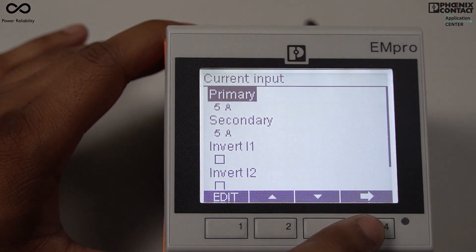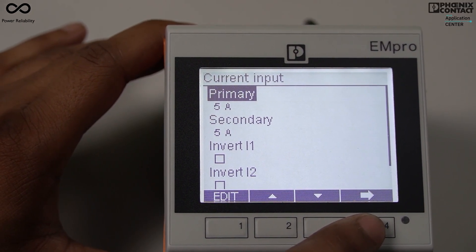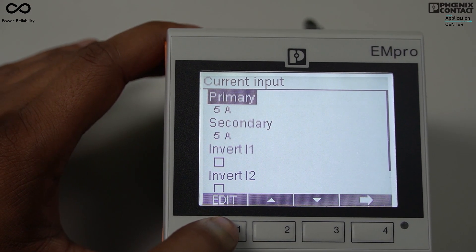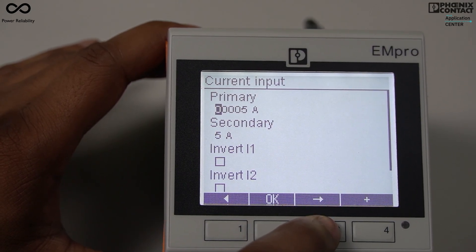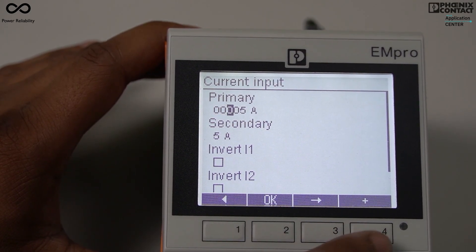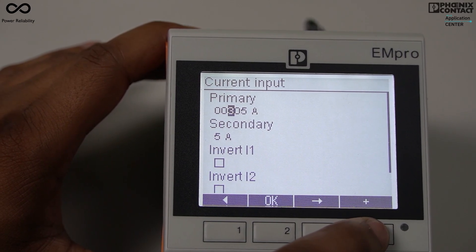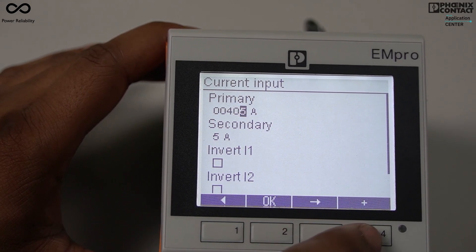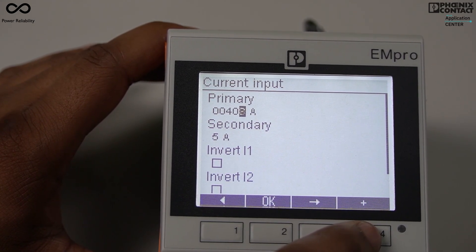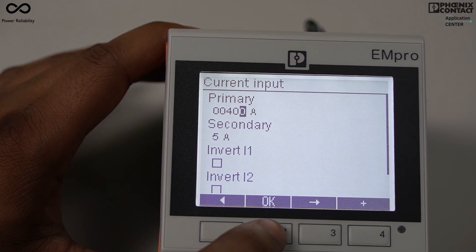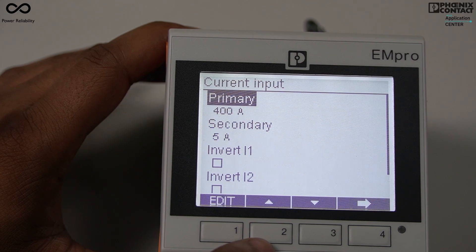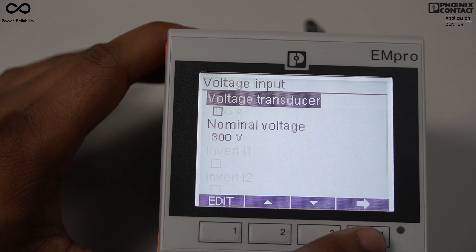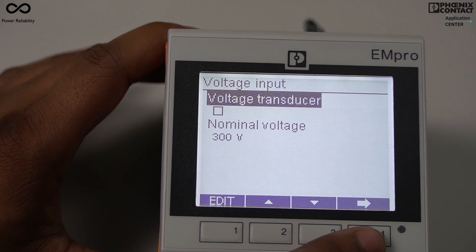Now I need to edit the current input. Suppose I want to make the CT ratio 400/5 — I will press the edit key, then move to the next digit. I will change the digits to make it 400 for primary and 5 for secondary, then press OK. The CT ratio is now programmed as 400 ampere by 5 ampere.